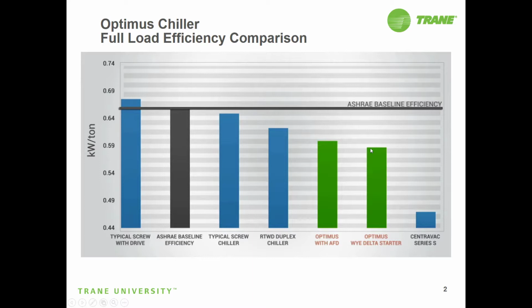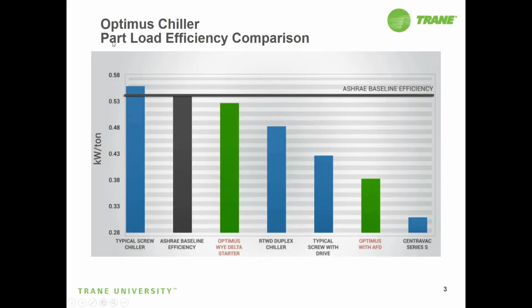Again, when you're running at full load, this extra power that is consumed through the drive into making our AC sine waves is noticeable when we're here at full load conditions. But all of these are well under the ASHRAE baseline efficiencies. And then finally, here's our CenTraVac Series S oilless chiller that is frequency driven, and obviously there's nobody in the industry that can get down lower than that for us. But the whole purpose of what we're talking about here is on this next slide.